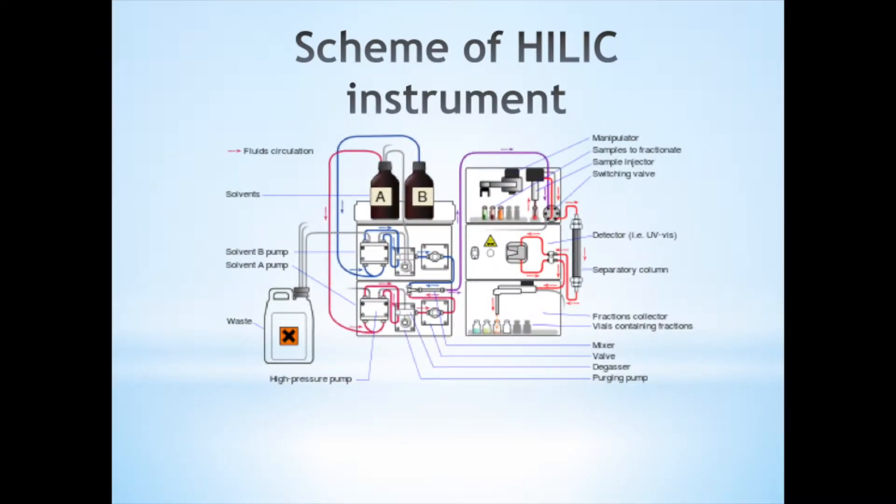HILIC is based on the HPLC instrument, but uses a hydrophilic column, which allows us to separate, identify, and quantify a mixture of compounds. The components of a basic high-performance liquid chromatography system are shown in the simple diagram above. A high-pressure pump is used to generate and meter a specified flow rate of mobile phase, typically milliliters per minute. An injector is able to introduce the sample into the continuously flowing mobile phase stream that carries the sample into the HILIC column.